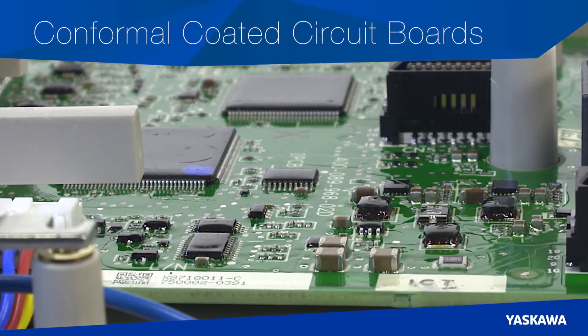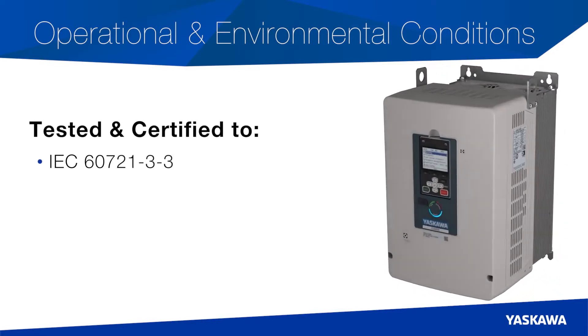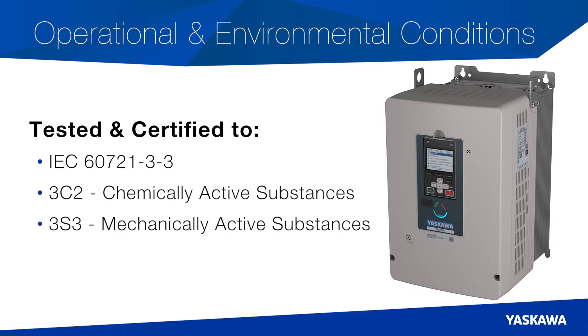This means reduced downtime and increased productivity. When it comes to product durability, we took extra measures to safeguard sensitive electronics by conformal coating all circuit boards. Tested and certified to IEC 60721-3-3 for operational and environmental conditions, the GA800 meets 3C2 and 3S3 for chemically and mechanically active substances, respectively.